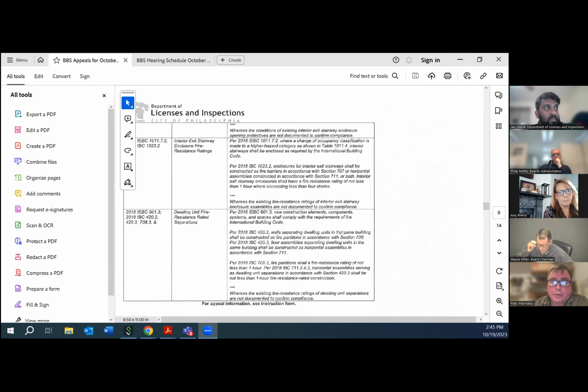Another item was the separation of the dwelling units, where the existing fire resistance ratings of those separations aren't documented to confirm compliance. They're required to be 1 hour separated. Since the building's construction wasn't observed, it's hard to certify that there's actually a 1 hour separation.